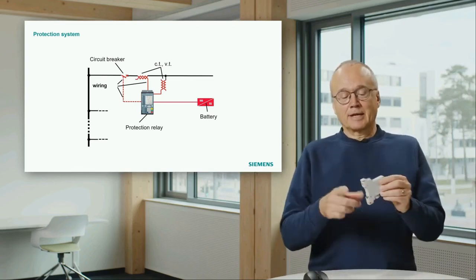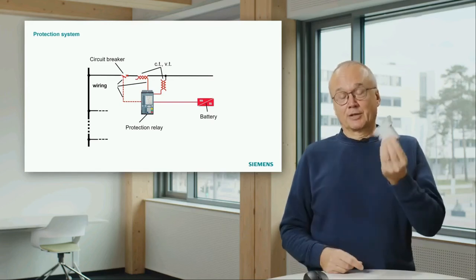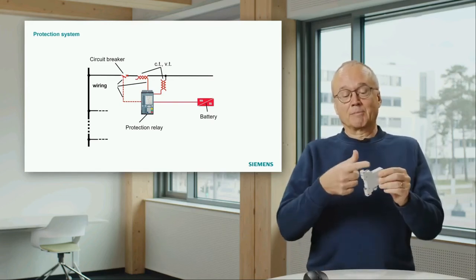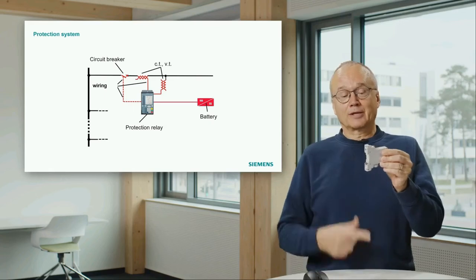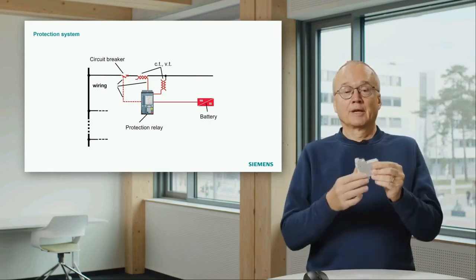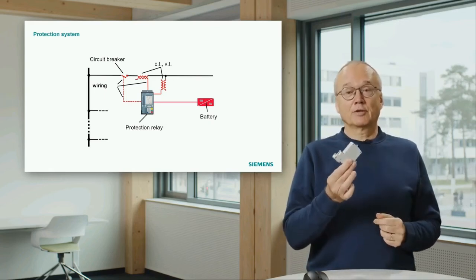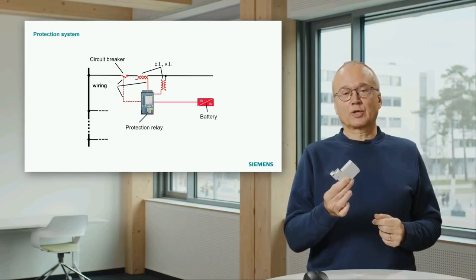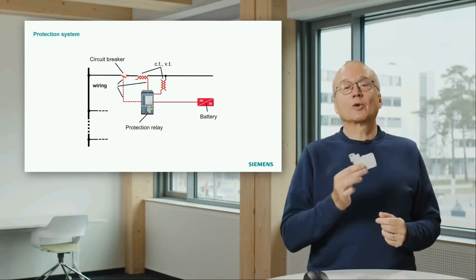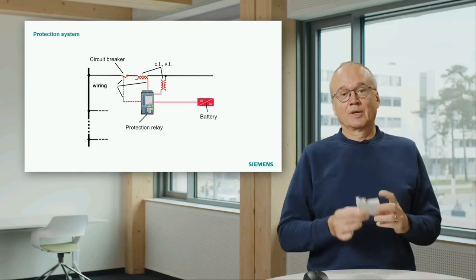This device here directly measures the current. In this case, it has only current. That means the current flows directly through this device. It makes the decision. If it says, okay, there is a short circuit, I will trip. It also interrupts the current.